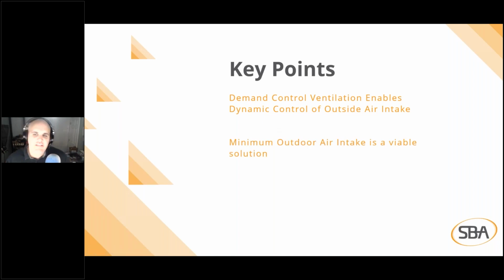Minimum outdoor air intake is a viable solution. It is viable. You hear so many folks who sing the praises of demand control ventilation, and granted, it is good. It is nice. It can save you energy in large spaces. It can reduce how much air you have to bring in the building. That being said, minimum outdoor air intake is still viable. All right, and finally, pressurization and flow can be used to drive IAQ.